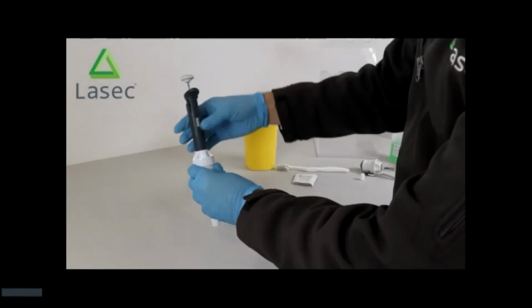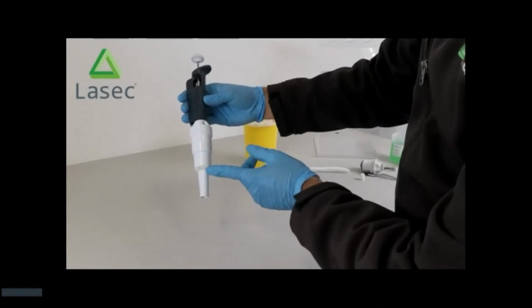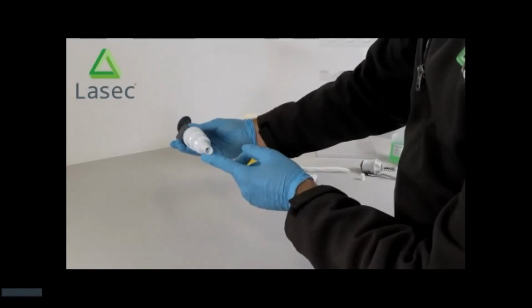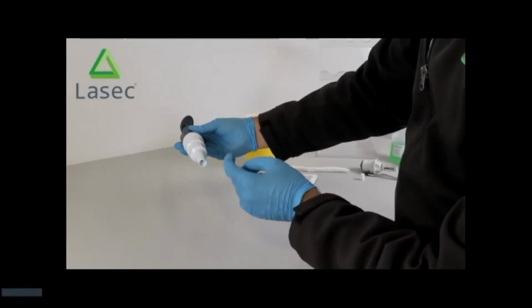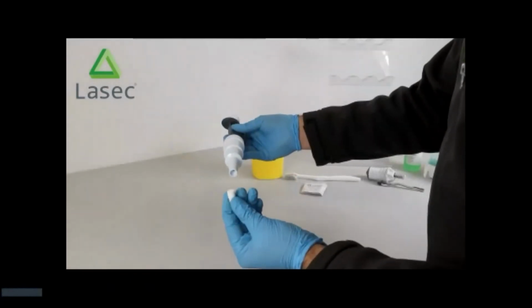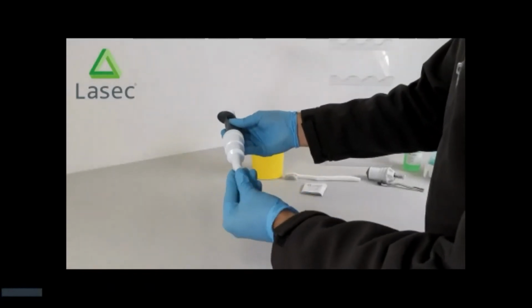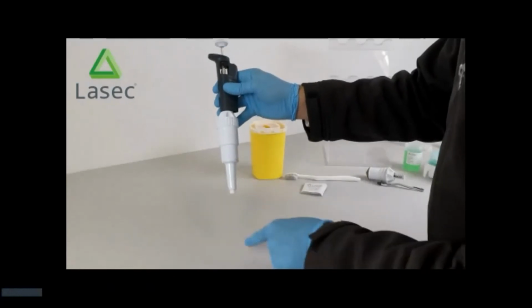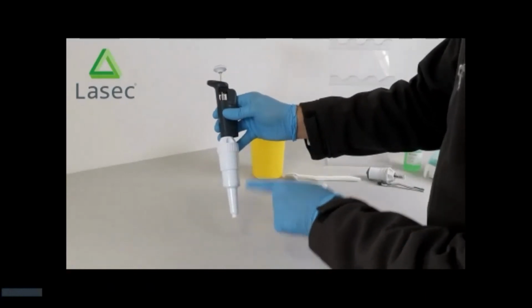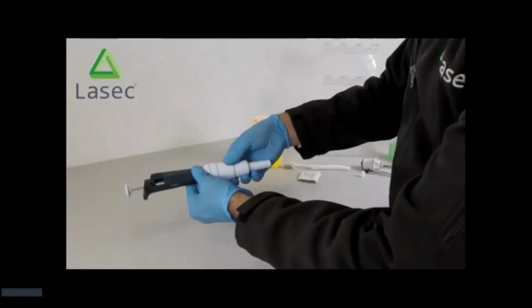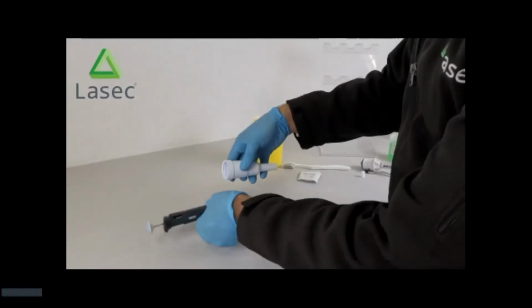So what I'm doing there is I'm checking that volume setting or the volume counter. I check both the thumb wheel, I check the head. And the reason I'm using a large volume pipette in this case is on purpose, because what we find is that there is a lot of damage caused by ingress of solution into large volume pipettes.